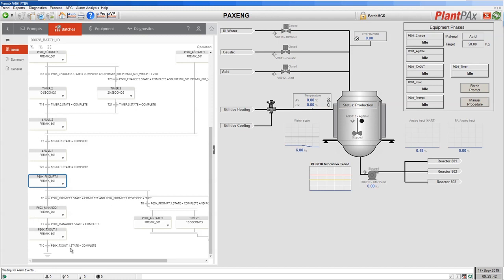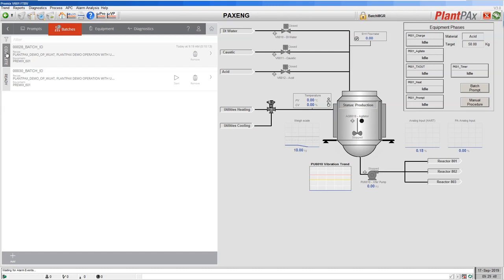Our recipe has now completed. The green box has moved from transfer out. If we go back to our batch list we can see that the recipe has completed. We now have another recipe ready for us to start. If we wanted to, we could have started all the recipes in the recipe list and it would have run them one after the other — the second recipe would have automatically been started as soon as the first completed. Everything undertaken by FactoryTalk Batch to execute recipes is recorded in a batch record for each batch. This is provided with standard out-of-the-box reports. Let's go and look at those reports now for the recipe that we've just run.